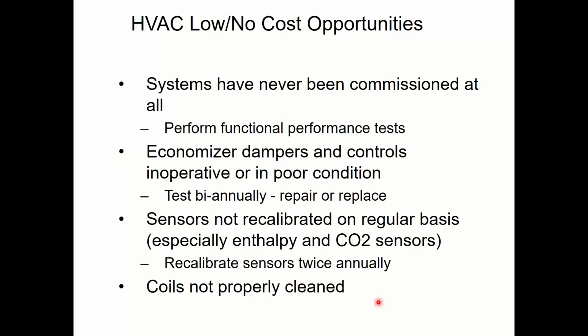The less debris I allow to get to the coil, the less things could be stuck on there and growing on there. In order for me to have mold, for example, grow on my coil, if you guys were on last week, you probably heard me say this, but I need 3 different things to grow mold. I need to have mold spores. Well, they're everywhere. They're in the air. That's pretty easy to find those guys. There's millions of them everywhere. I need to have moisture. Well, there's plenty of moisture on an evaporator coil because that's literally its job, to pull moisture out of the air and drain it away. So definitely have moisture available.